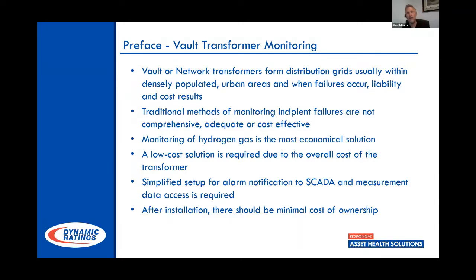One of the main problems we were having was we had so many of these transformer vaults, and I think Memphis is sitting on about 605 network transformers, or at least when I was there, somewhere in that range. And I did not have the manpower to go in and do the inspections as frequently as they needed to be done to these transformers. I mean, we did do an inspection, and being out in the industry and talking about how some other people handle the service of these transformers, we actually had a very good program in place concerning doing the maintenance of these, which is something I'll cover real quick, and I don't want to spend too much time because I need to get in the conversation.